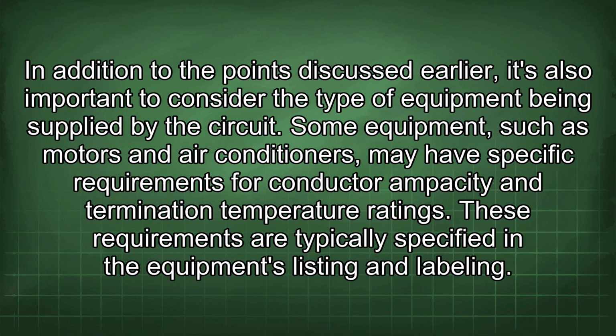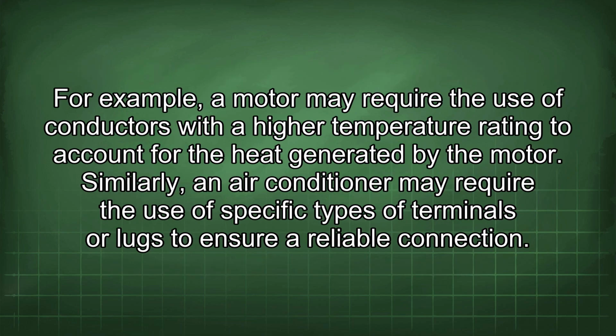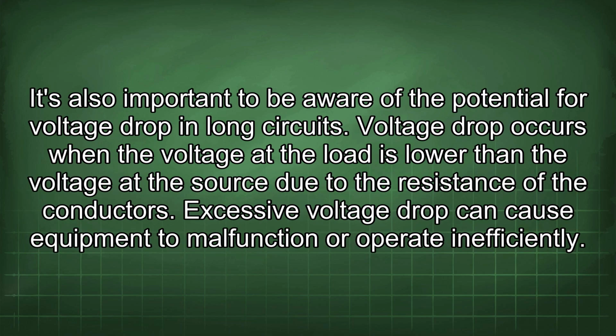These requirements are typically specified in the equipment's listing and labeling. For example, a motor may require the use of conductors with a high temperature rating to account for the heat generated by the motor. Similarly, an air conditioner may require the use of specific types of terminals or lugs to ensure a reliable connection. It's also important to be aware of the potential for voltage drop in long circuits.